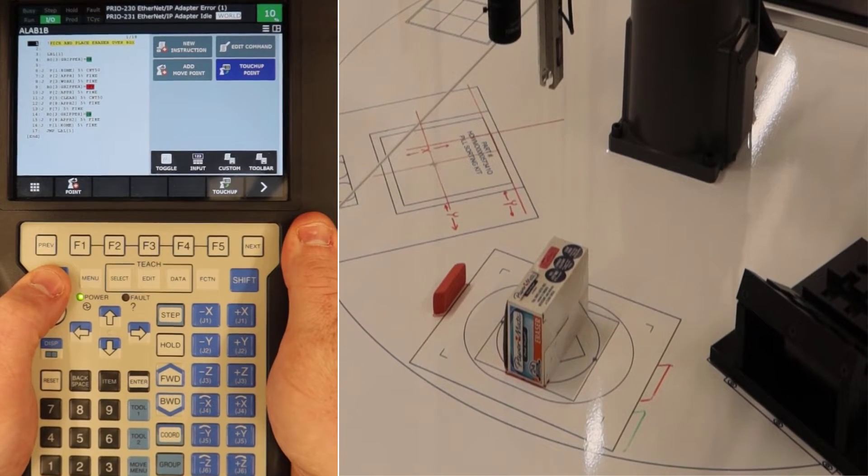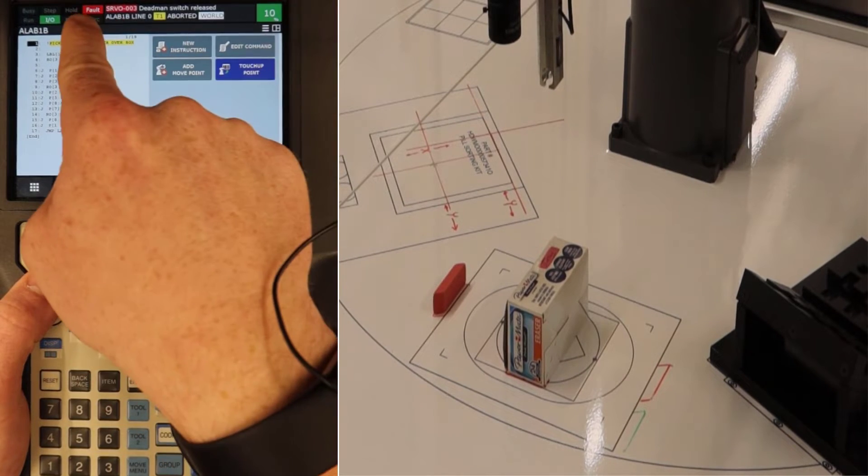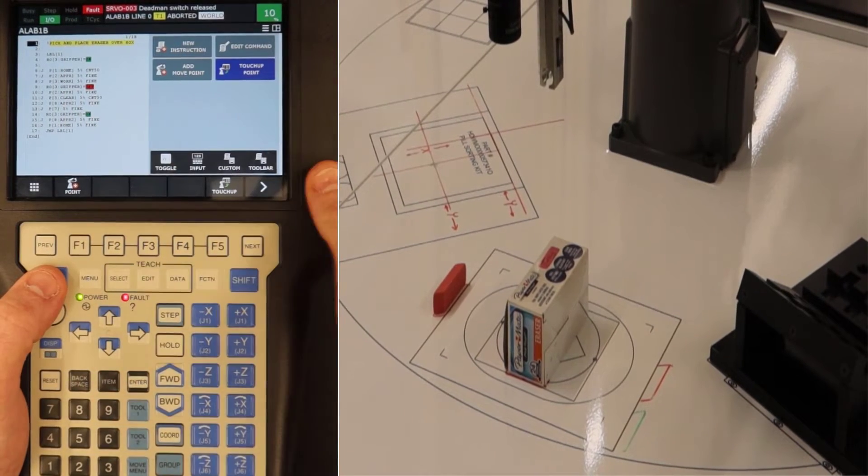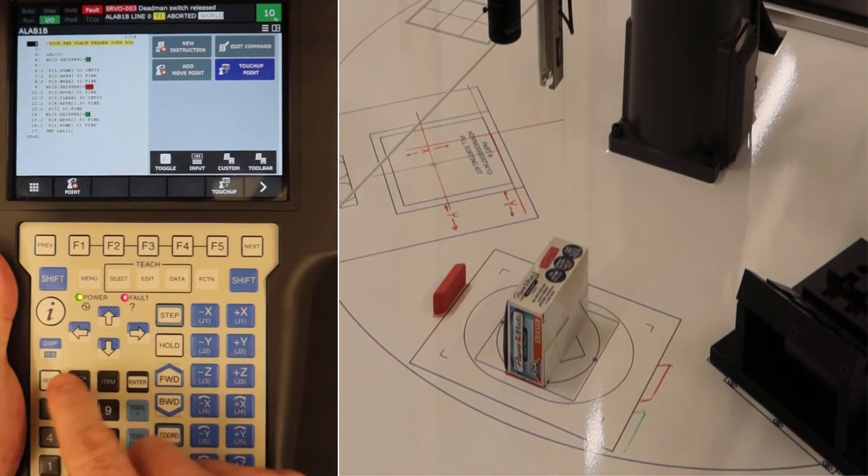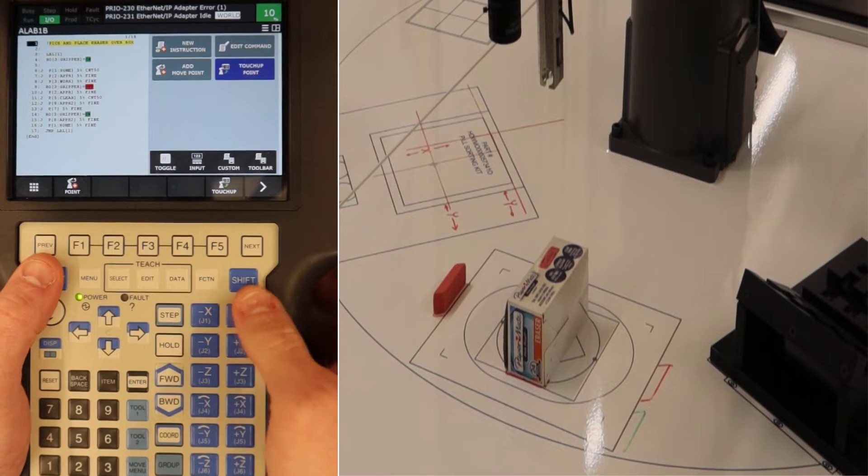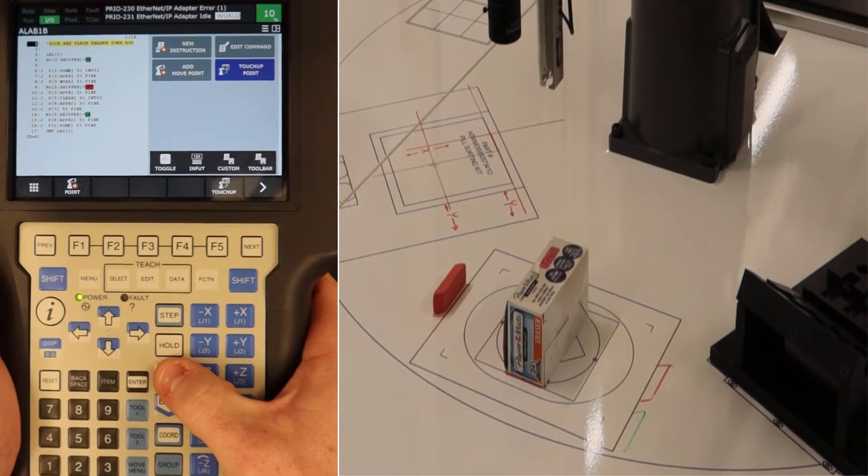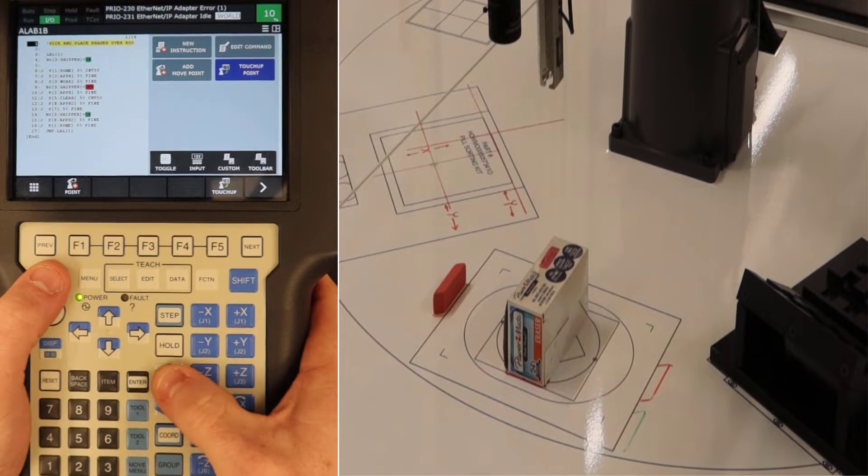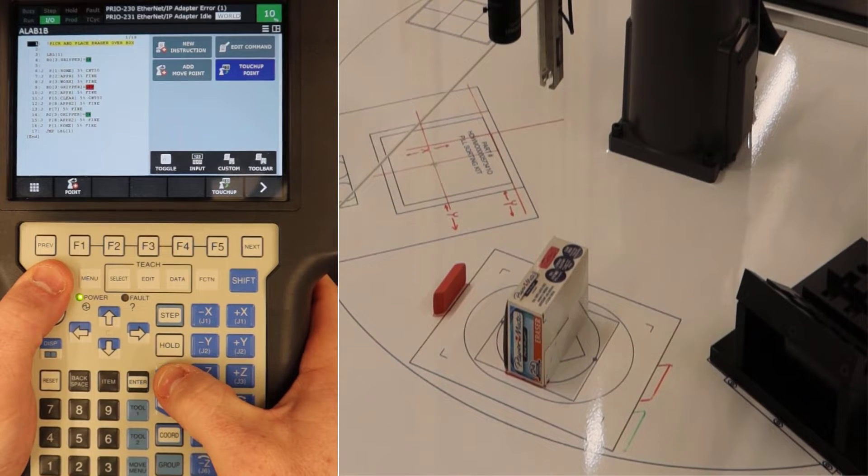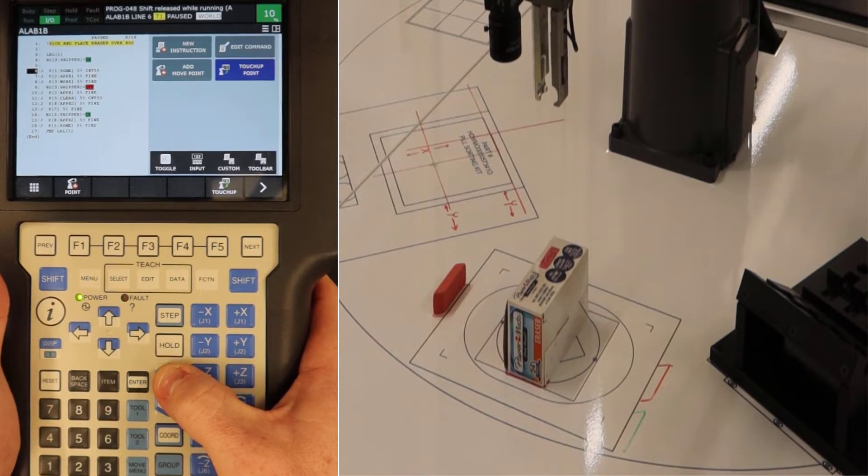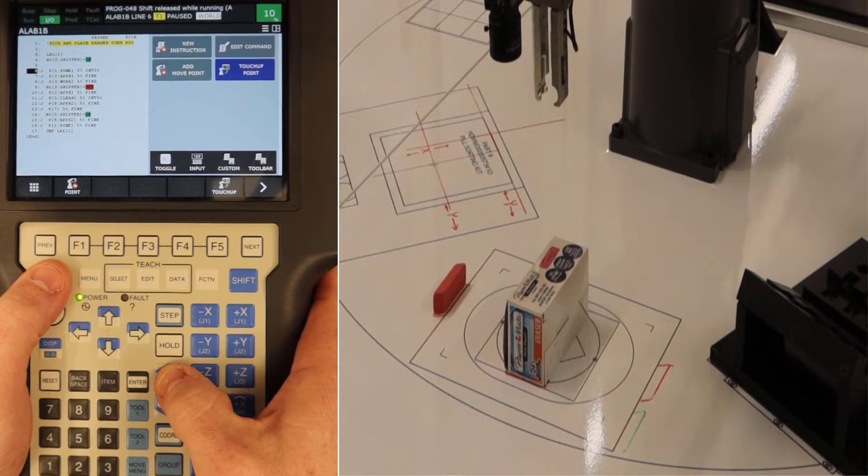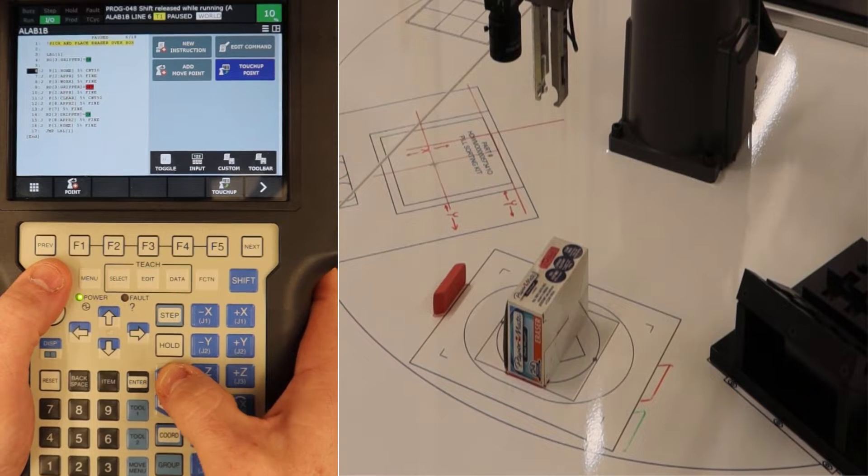But just like with letting go of the dead man switch, we also see a fault and then a servo error. Dead man switch released. That's when I put it in, hit reset. Even if I try to run a program, it's not working because I'm not holding down shift. But if I start a program and I let go of shift, it's going to tell me the shift button was released while running. So these are just a couple of different things to keep an eye out for when you're working on the teach pendant.